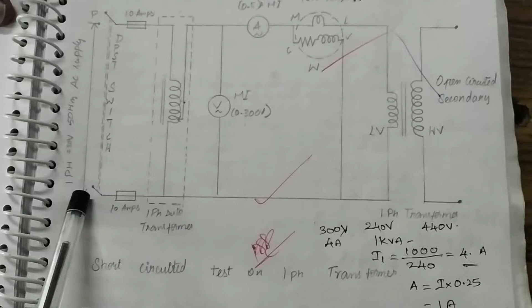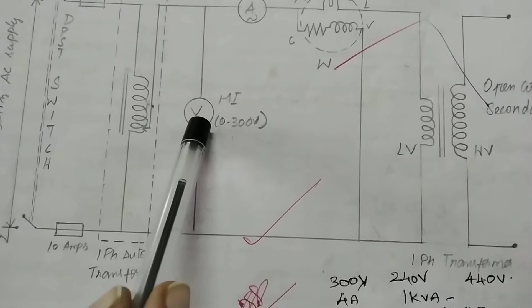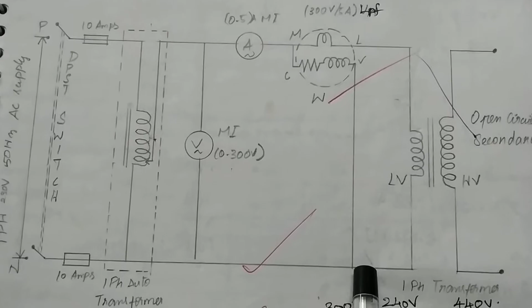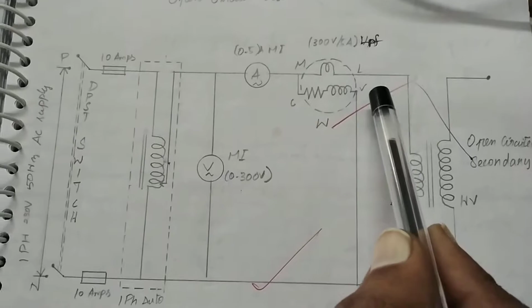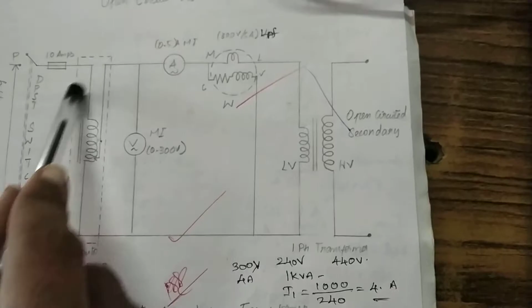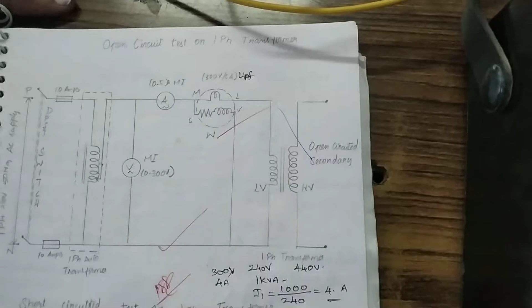Now we see the neutral connection. From the neutral, you connect it to the 300 voltage terminal of the voltmeter, that range is selected. Again from that 300 terminal, you connect to the 300 voltage terminal in the wattmeter. After that, connection is taken from V of the wattmeter to the LV side neutral. This completes the connections. You have to leave the HV side open, you don't need to do anything there.